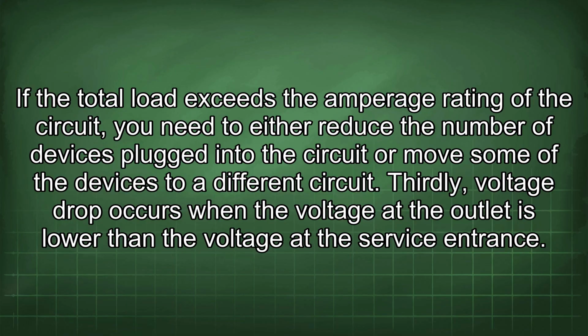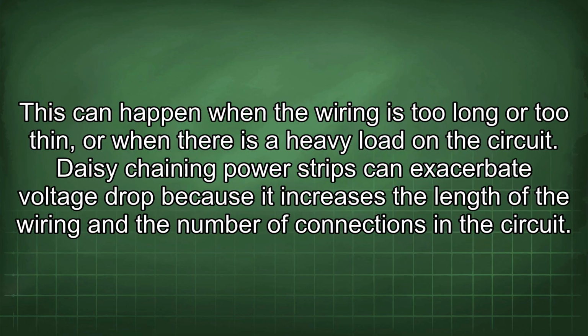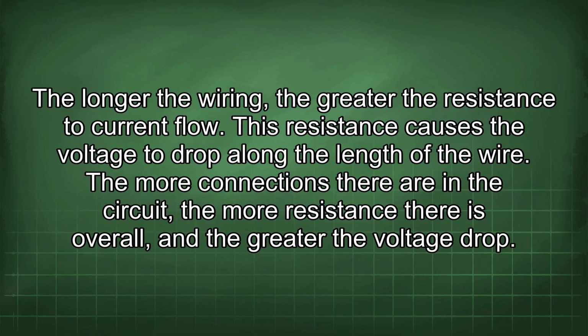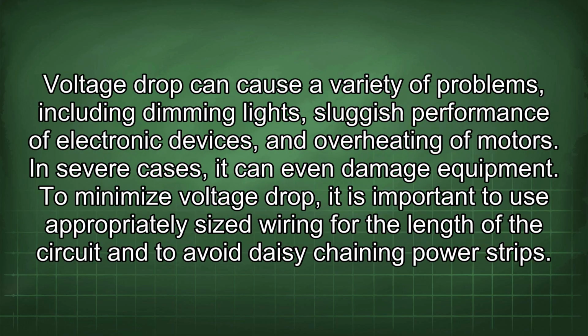Thirdly, voltage drop occurs when the voltage at the outlet is lower than the voltage at the service entrance. This can happen when the wiring is too long or too thin, or when there is a heavy load on the circuit. Daisy chaining power strips can exacerbate voltage drop because it increases the length of the wiring and the number of connections in the circuit. The longer the wiring, the greater the resistance to current flow. This resistance causes the voltage to drop along the length of the wire. The more connections there are in the circuit, the more resistance there is overall, and the greater the voltage drop. Voltage drop can cause a variety of problems, including dimming lights, sluggish performance of electronic devices, and overheating of motors. In severe cases, it can even damage equipment.